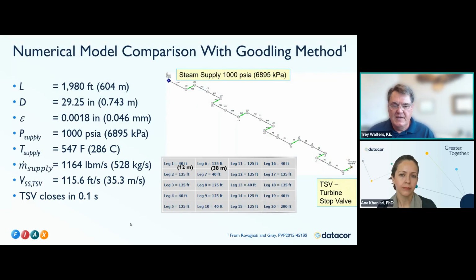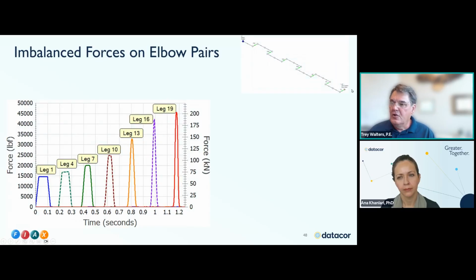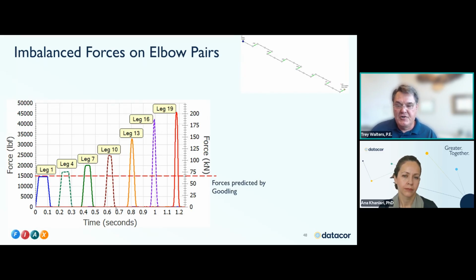This is a particular example that came from a paper done by some engineers at Sargent and Lundy on the nuclear industry. It's a 1,000 PSI, 7,000 kilopascal steam supply. The piping is about 2,000 feet long, 600 meters, and the steam turbine stop valve is down here and closes. Going down from the turbine stop valve, these different green areas are where we predicted the forces. This is the force prediction from a comprehensive calculation using xStream. This was the force predicted by the traditional Goodling method.